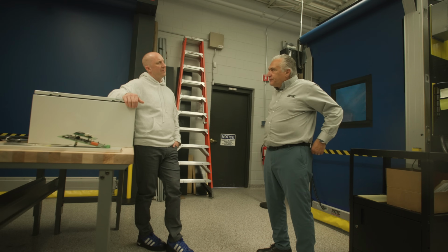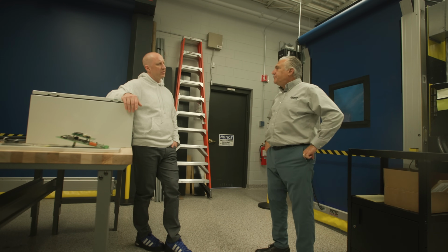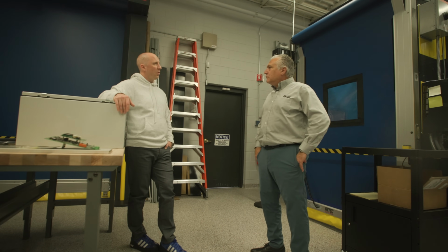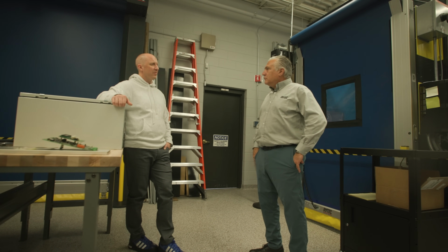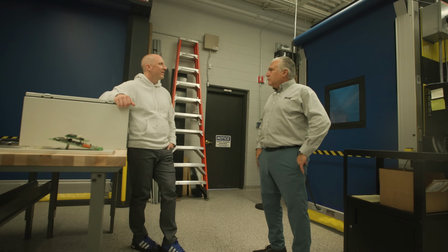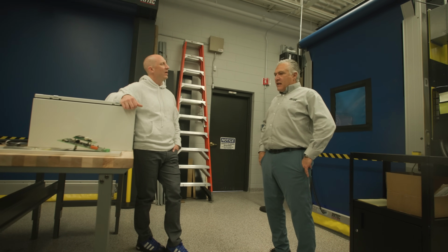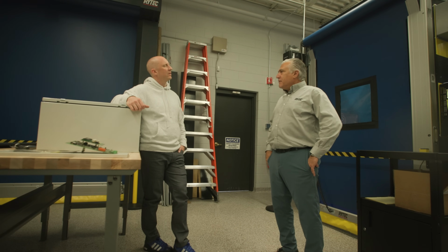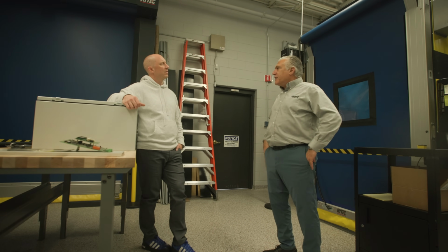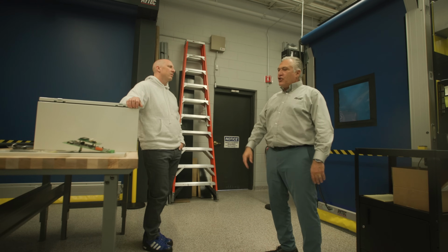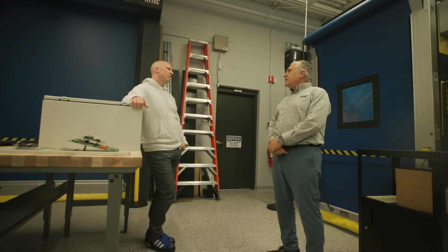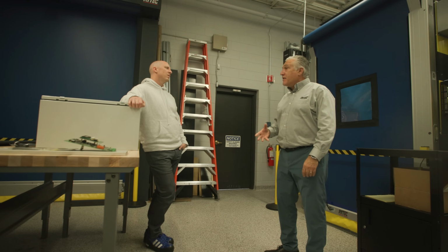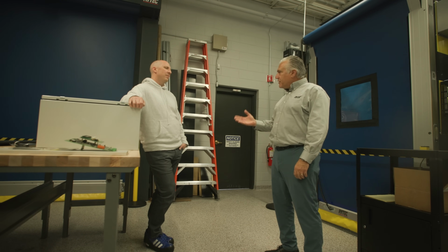Would you rather have a 230 single phase, or would you rather have a 3-phase converter on the door? If I had a good 230 volt single phase, I would not recommend a 3-phase converter. So if it was a private garage or whatever, in general, I would say no, you're good, as long as the wire that's providing the power to the door is sufficiently sized, number 4, so it doesn't sag.